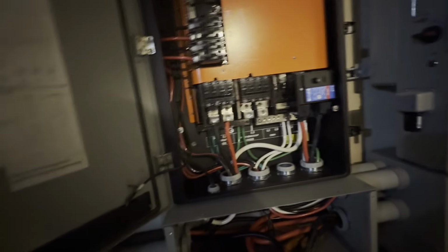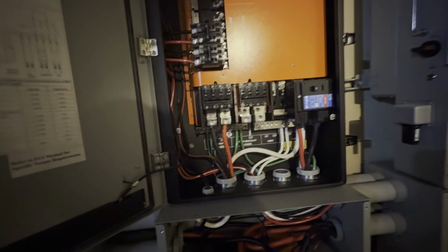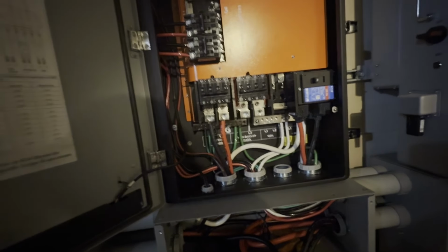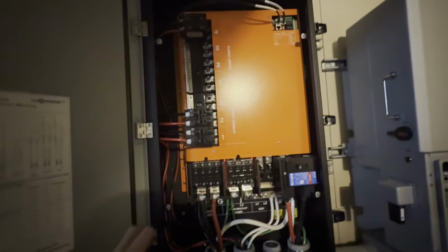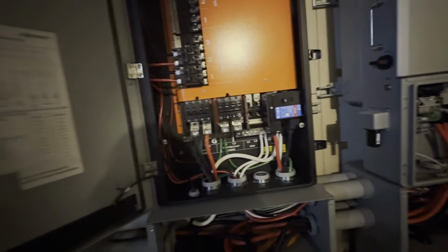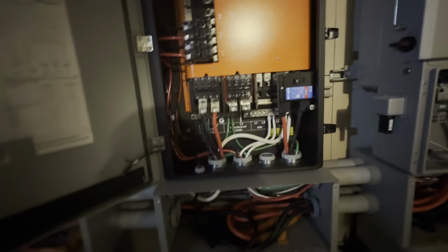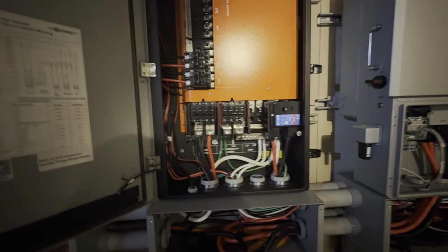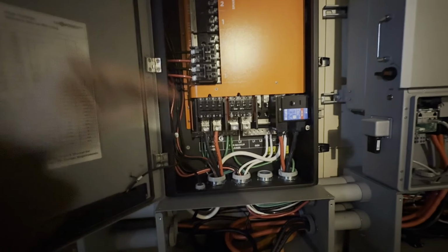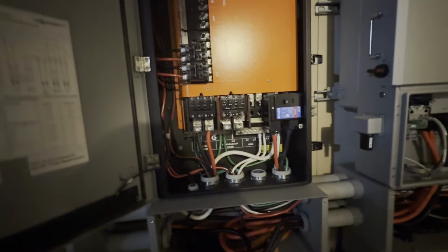In the future, I might get a generator, like a propane or gas generator or something like that. In that case, I can put a breaker here, and the MID can also be configured like, oh, the grid's down, the batteries are low, turn on the generator, and then, you know, once the batteries are at some level, I can say, okay, turn the generator off again.